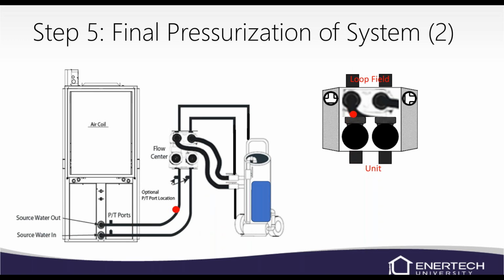I would probably stick somewhere between 40 and 60 PSI. If when you deadhead the pump you've got more than a 2-inch drop in your tank on your flush cart, you still have air in the system. You can also shut off your flush cart, and if it pushes back and overflows, then you know there's air in the system. Or if you see bubbles coming back when you shut off, you may want to wait a few minutes before you look for those bubbles, but if bubbles come back when the flush cart is off, then you know there's still air in the system as well.